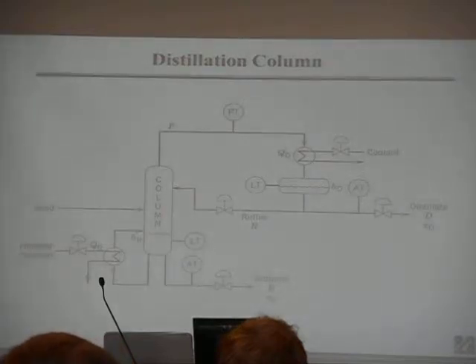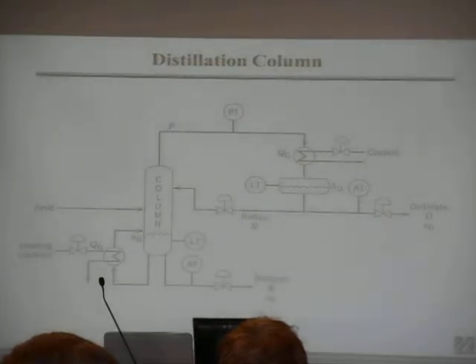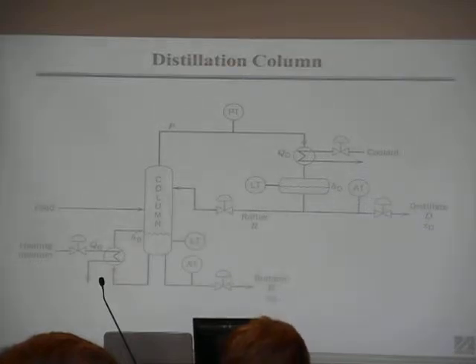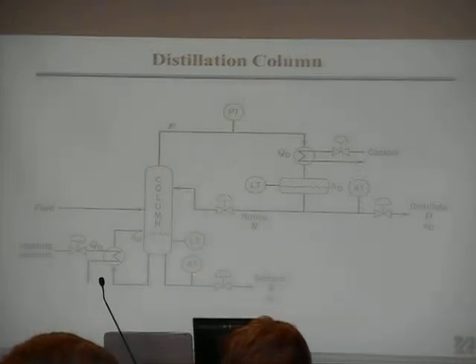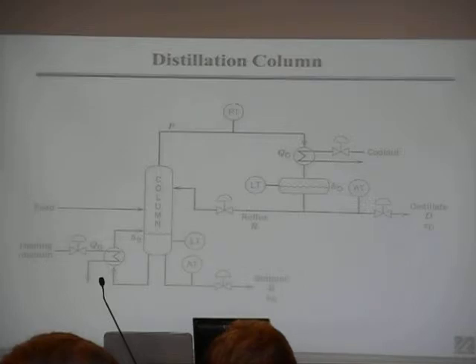Unless you do something like FTIR, but typically if you do GC you have to sample it, so you need a sampling system. It takes the sample to where the GC is — you can't have a GC sitting next to a plant out in the rain. So it's in a little house with other GCs, and you pipe the sample all the way there. That takes a lot of time, and the sampling system doesn't work — it gets clogged, the GC quits working. Lots of things can go wrong.